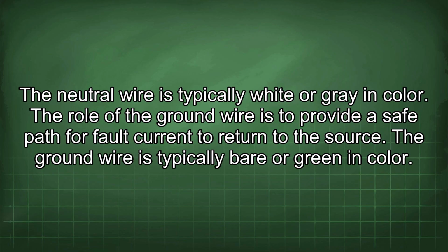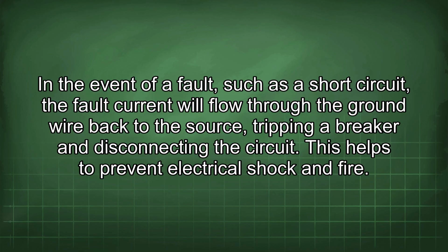The role of the ground wire is to provide a safe path for fault current to return to the source. The ground wire is typically bare or green in color. In the event of a fault, such as a short circuit, the fault current will flow through the ground wire back to the source, tripping a breaker and disconnecting the circuit. This helps to prevent electrical shock and fire.